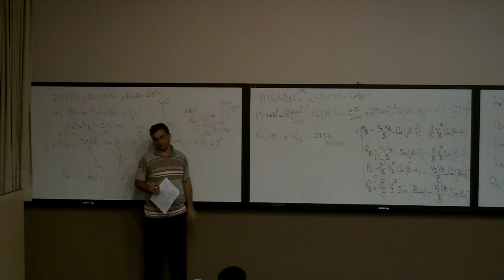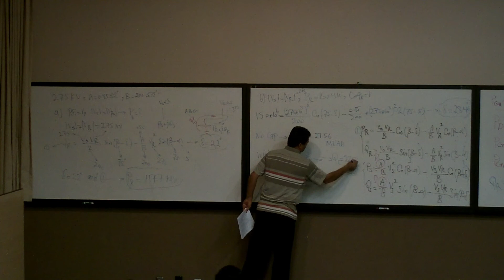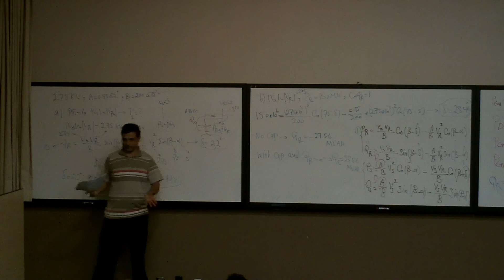Basically Q here will be 0, and this capacitor will be 27 or whatever. So, with cap, QR is 0, so basically QC should be 27.56. I calculated how much Q, if I'm going to have a flat voltage with 150 megawatt, Q is going to be this much. But I'm saying no, I want a unity power factor, so I have to generate this much with something else. I put the capacitor, right?